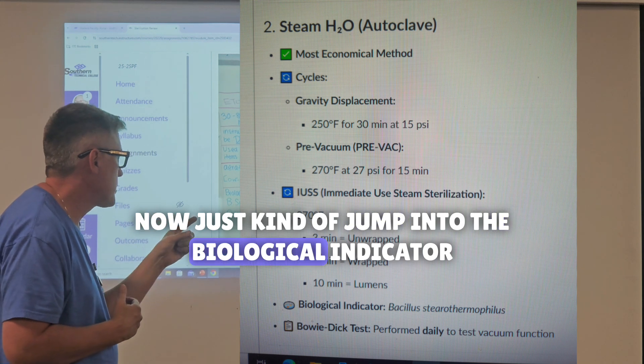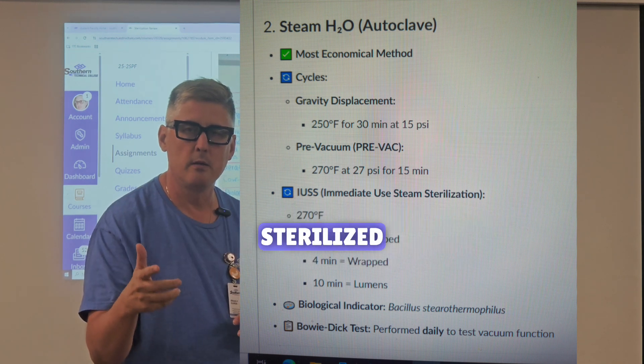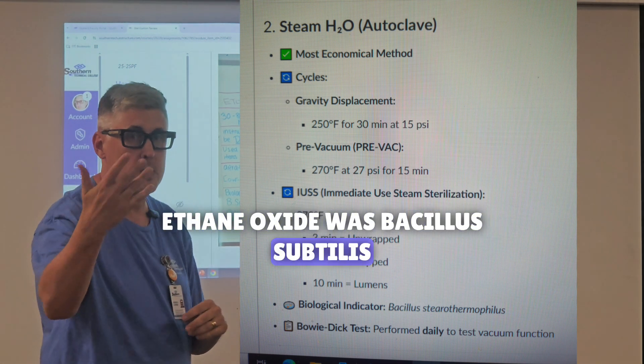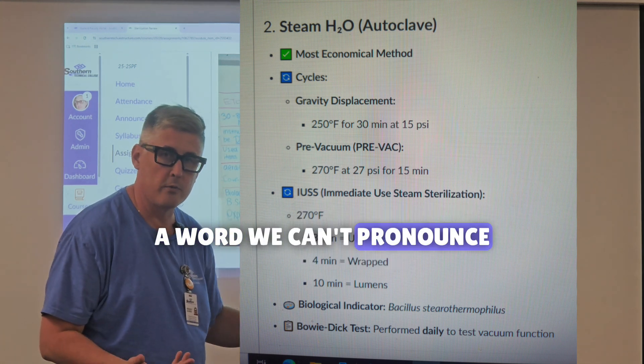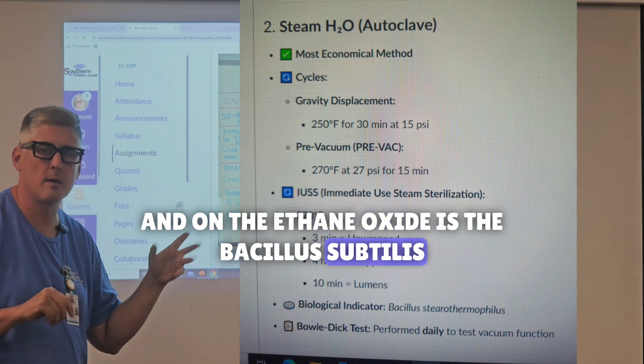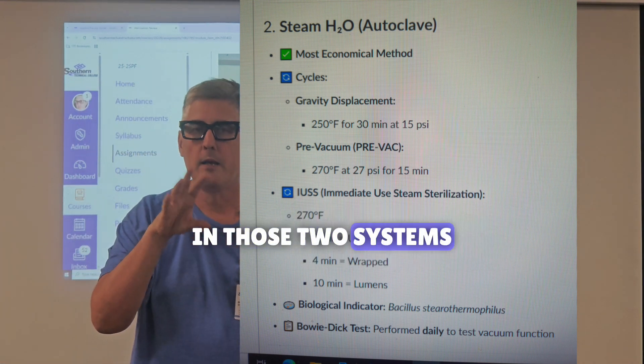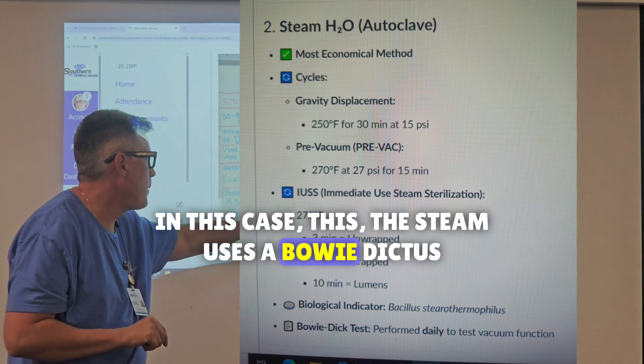The biological indicator is the most reliable way to prove something's been sterilized — we need a live bacteria. Ethylene oxide uses Bacillus subtilis. For steam, it's Bacillus stearothermophilus — a different type of Bacillus bacteria. So remember: those two different bacteria are used in those two different systems, and those are definitely on the CST all the time. Also, steam uses a Bowie-Dick test.